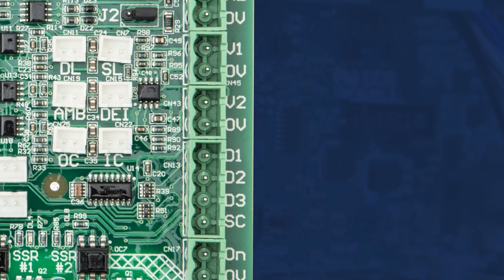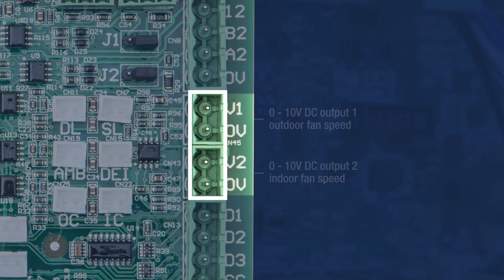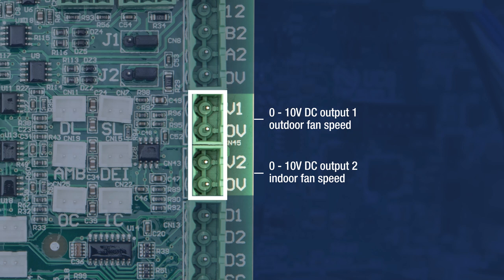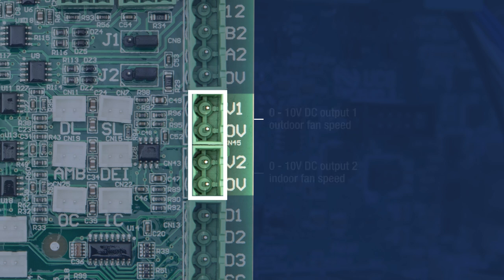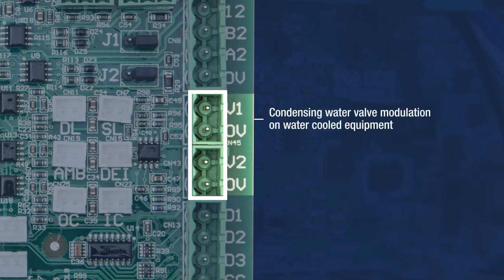The V1, V2, and 0V terminals are a 0-10V DC analog output used to control the outdoor fan speed in the case of V1 and indoor fan speed for V2. V1 can also be used for condensing water valve modulation on water-cooled equipment if one is installed in the field.